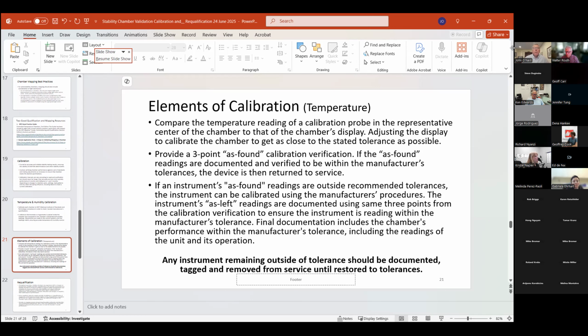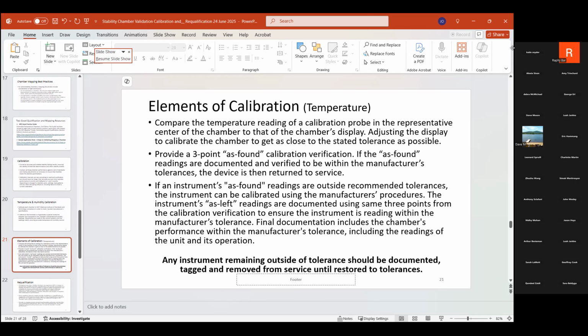If the as found readings are documented and verified to be within the manufacturer's tolerances, the device is then returned. But if the instrument's as found readings are outside the recommended tolerances, the instrument can be calibrated using the manufacturer's procedures. And the instrument's as left readings, when they're all done, are documented using the same 3 points from the calibration verification to show that there was equality in the measurements. And then final documentation includes the chamber's performance within the tolerance, including the readings of the unit and its operation.